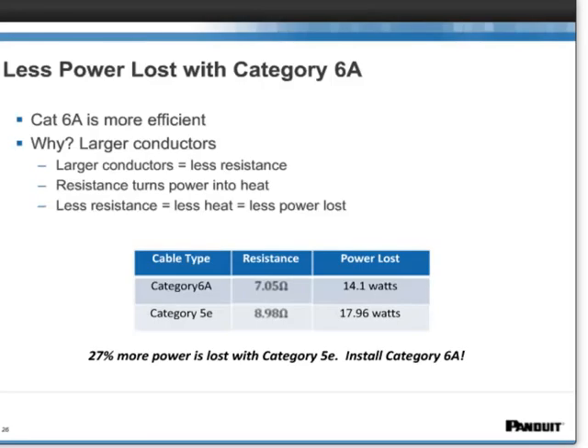To mitigate some of the heat concerns with PoE, we recommend that you use Cat 6A cable. Cat 6A cable is far more efficient due to its larger conductors. Larger conductors offer less resistance. The more resistance you have, the more power you will lose to heat. Less resistance equals less heat equals less power lost. Ultimately, we found that you lose 27% more power with Cat 5e cable versus Cat 6A when deploying Power over Ethernet.